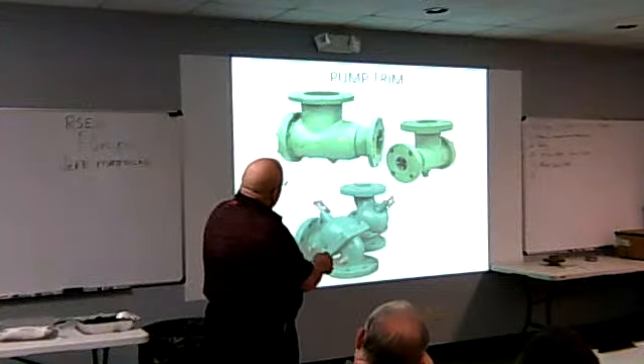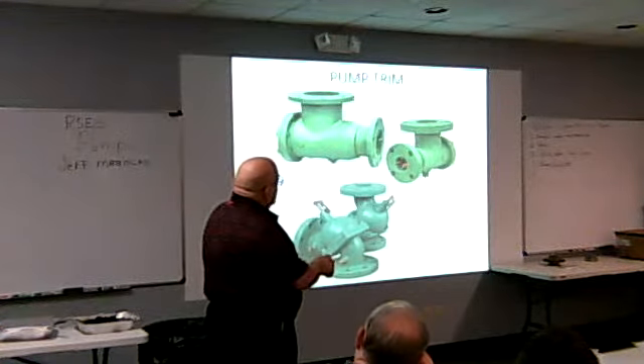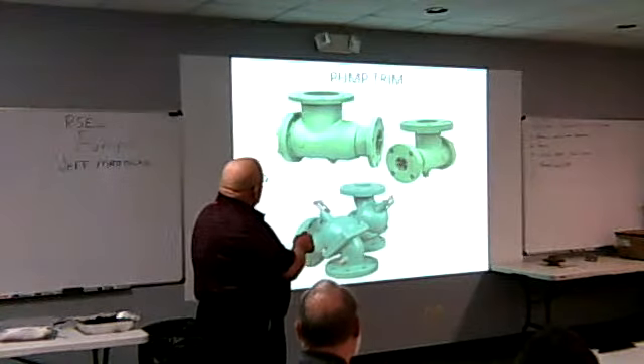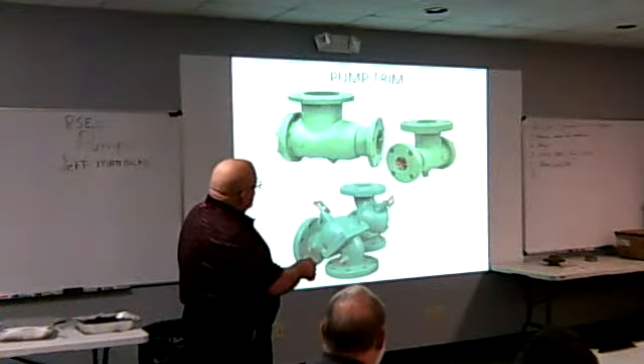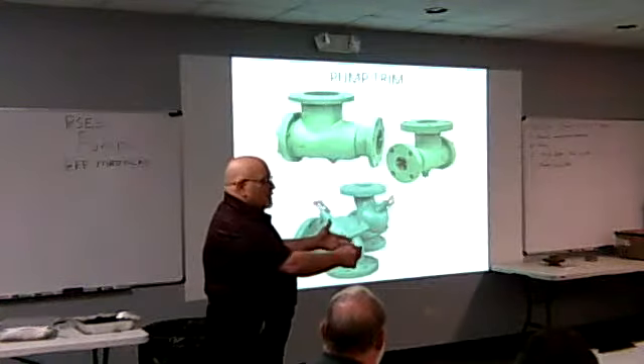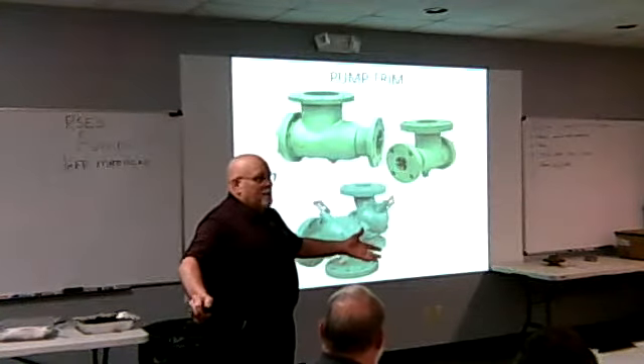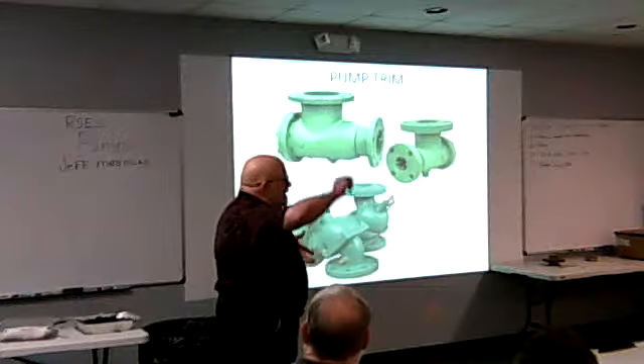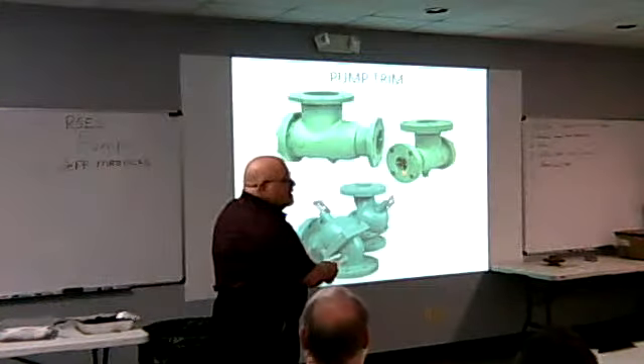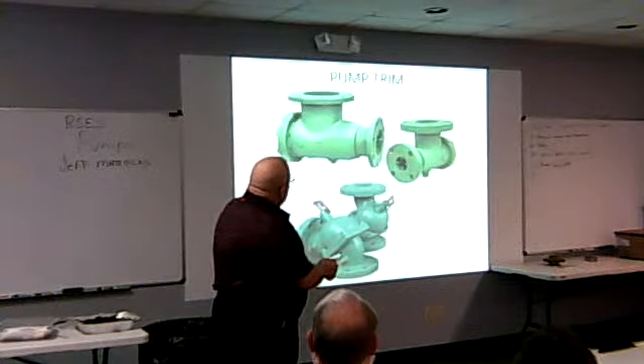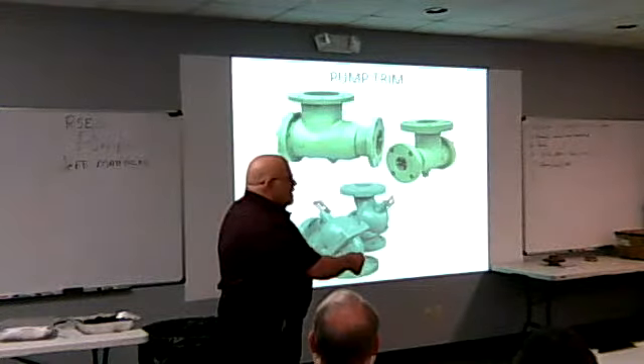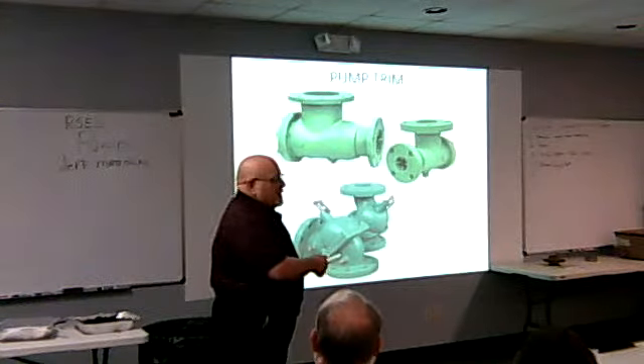This allows the straightening vanes in here. If you look inside here, see these vanes? When this water comes in and turns 90, this gives you that laminar flow we're looking for while we have the 5 to 8 pipe diameters. Otherwise it would be turbulent; it comes in and this straightens the flow out. And those vanes, when you open this, you can pull out. You can replace the vanes, you can replace the strainers.